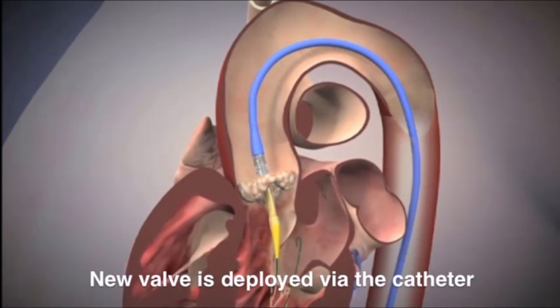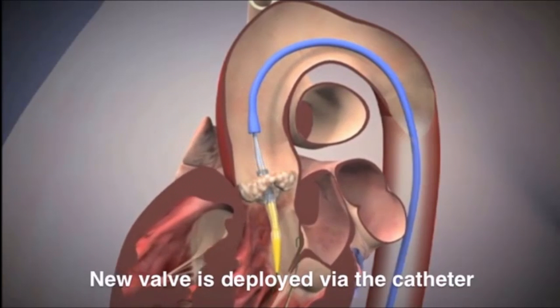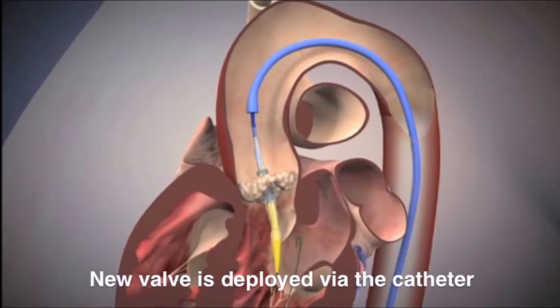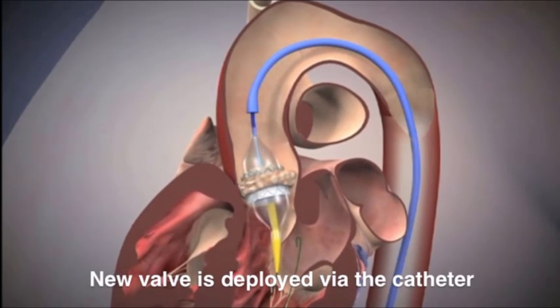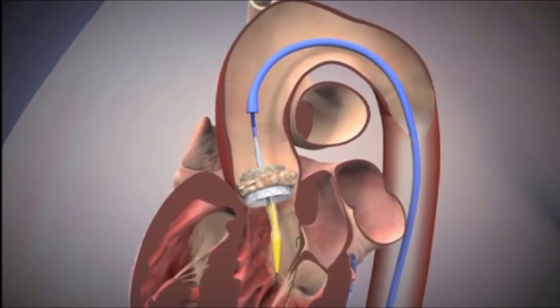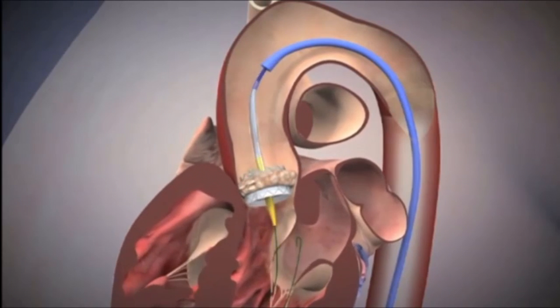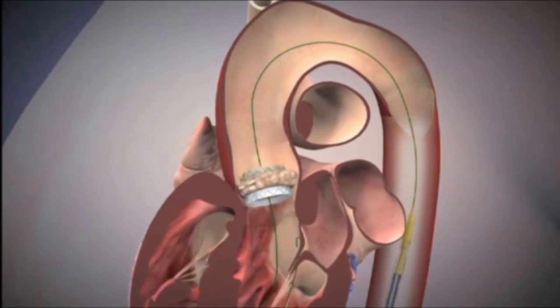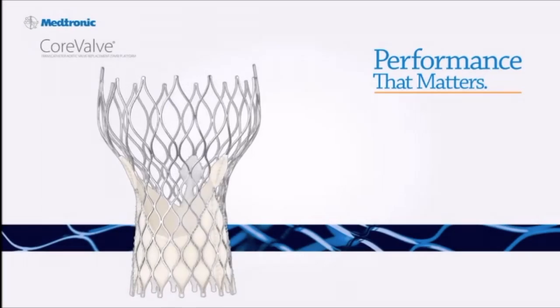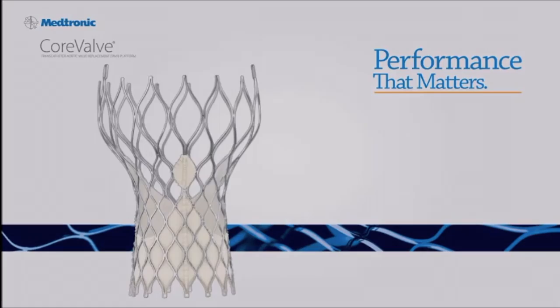Previously, TAVRs were built with stainless steel frames, such as the Edwards Sapien valve. It is able to be expanded with balloons at a procedure called aortic balloon valvuloplasty. There is currently research being done on the development of a new TAVR with a superelastic nitinol frame. One example of this is the Medtronic CoreValve.